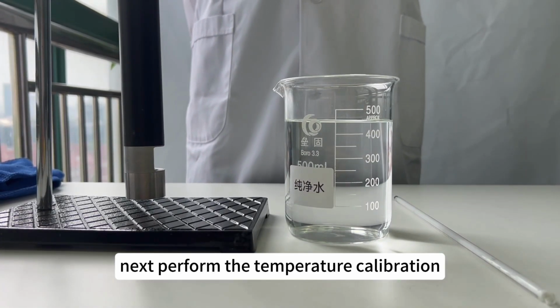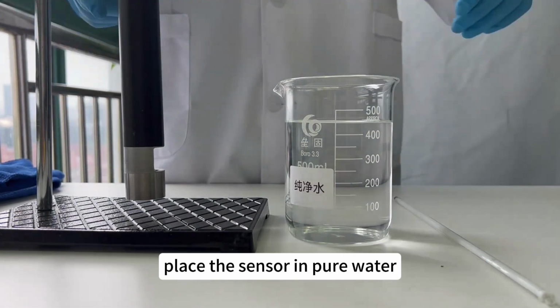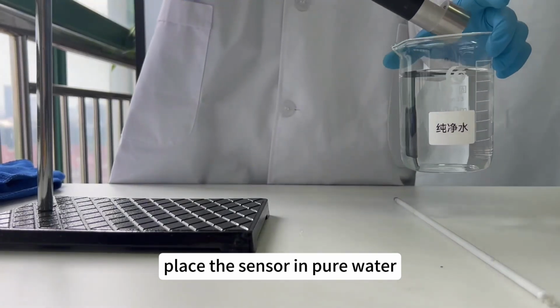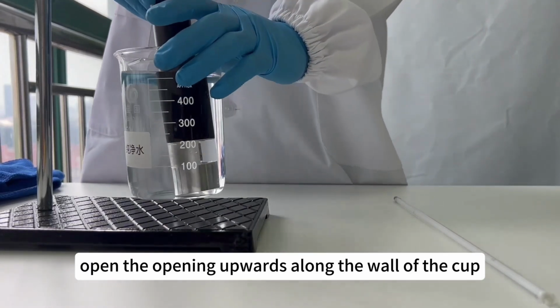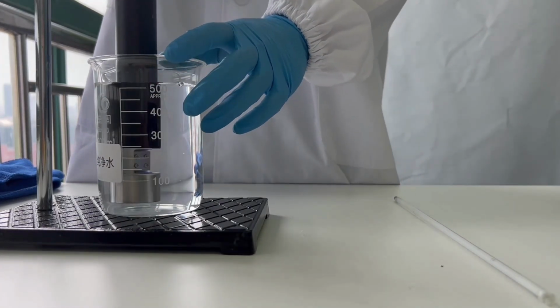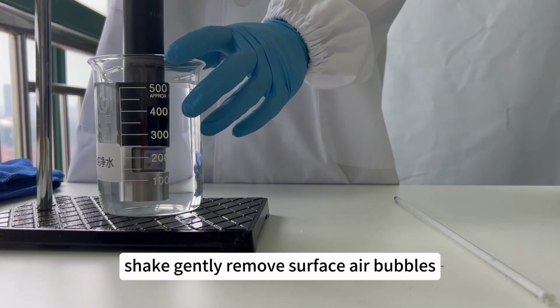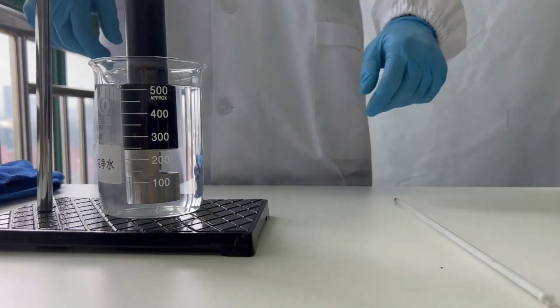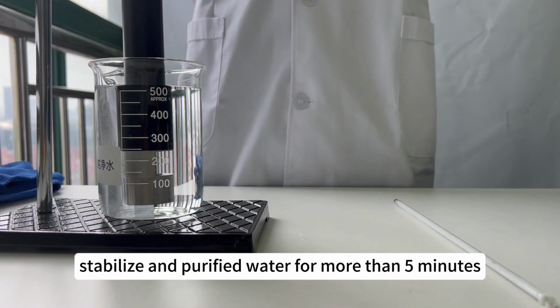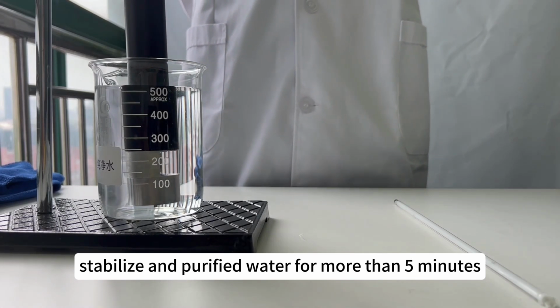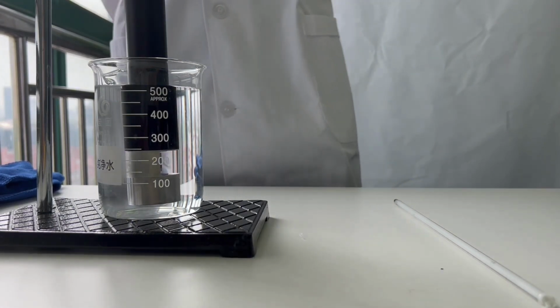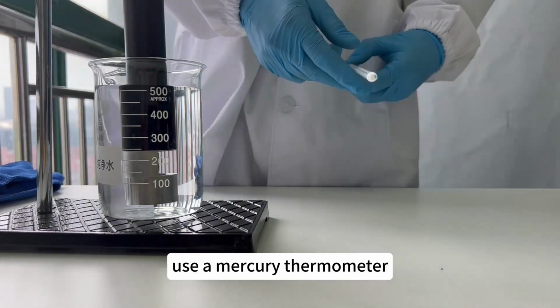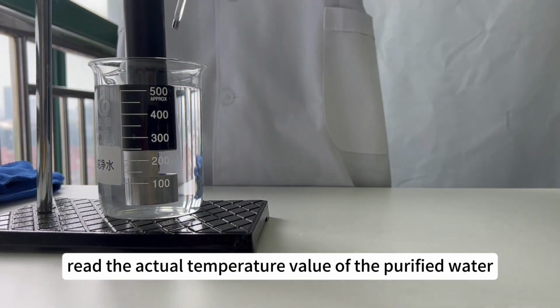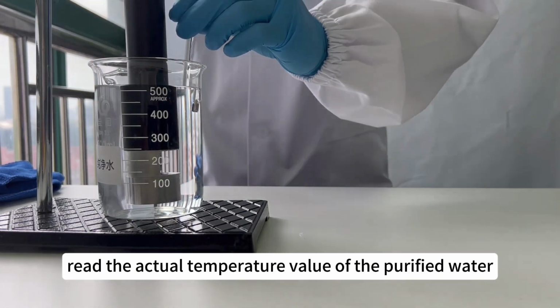Next, perform the temperature calibration. Place the sensor in pure water. Open the opening upwards along the wall of the cup. Shake gently. Remove surface air bubbles. Stabilize in purified water for more than 5 minutes. Use a mercury thermometer. Read the actual temperature value of the purified water.